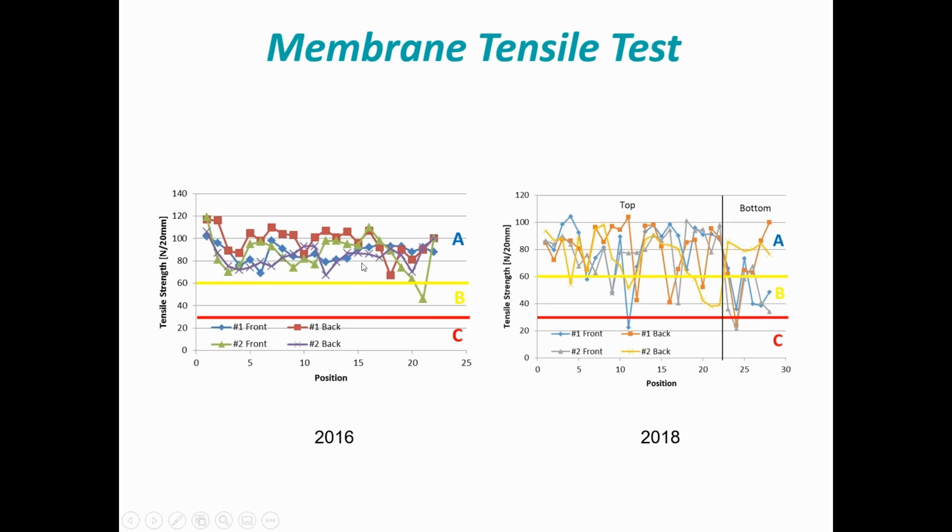Most of them were still in the 80 to 100. I told them, hey, there was one data point a little less than 60%, but I think you can keep operating. They operated for another 2 years. And in 2018, we had a lot more data points, and this same plant was a little bit lower than 30%. And they replaced the membrane in 2019.